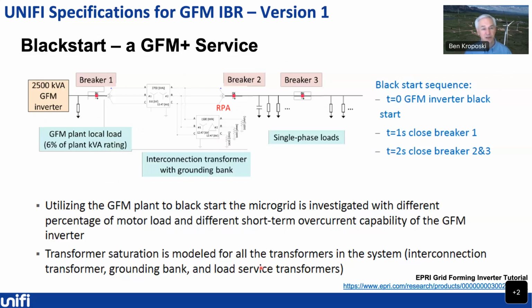Black start. Now that could be considered maybe a grid forming plus service. We know that they can create their own voltage waveform, but do they really have the capability to do complete black starts? That's a different question, because now you're adding in the ability to restart transformers from cold or re-energize lines. And these things are important to take care of in terms of the capability of the sources that you may have in there. So there's information around how best to start using grid forming technologies for black start capability.